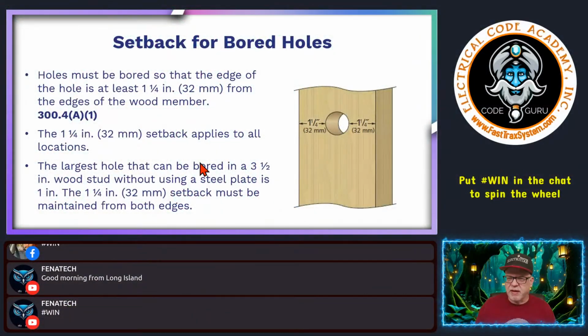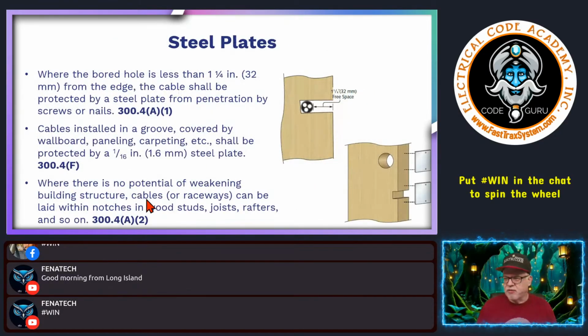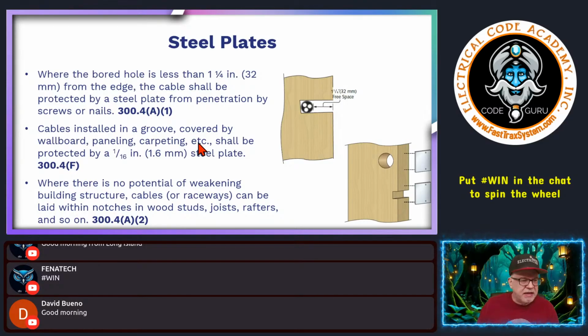All right, so that's what we're dealing with. Now, when we're talking about those steel plates, where the bore hole is less than 1.25 inches from the edge, the cable shall be protected by a steel plate from penetration by screws or nails. That's 300.4(A)(1). That steel plate needs to be at least 1/16 of an inch, or it could be listed. If it's a listed or marked steel plate, it may be less, but it is listed, possibly listed as a nail plate for this application. Other than that, we're going to have a steel plate of at least 1/16 of an inch.